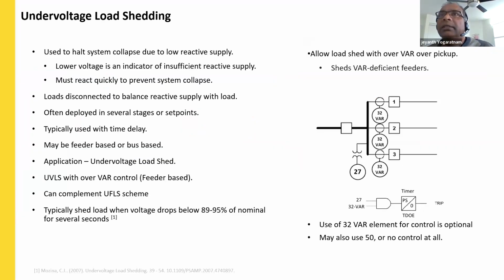The other one I like to emphasize is under voltage load shedding, which works on a simple principle. There are loads which consume reactive power, and that reactive power needs to be fed by the generating sources. If the reactive power is not sufficient to feed the load, it will bring down the voltage of the bus or the point of common coupling. If the generators cannot inject more reactive power to the bus, the only way we can bring the voltage back to normal is by load shedding. In this particular case, we will be using under voltage load shedding with the supervision of a reactive power element.